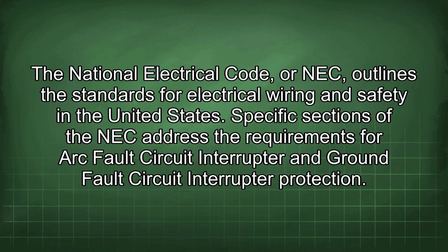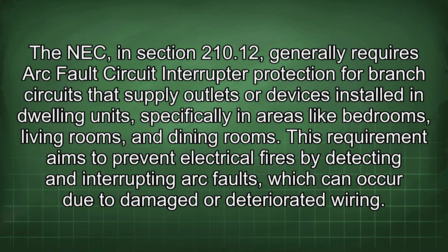The National Electrical Code, or NEC, outlines the standards for electrical wiring and safety in the United States. Specific sections of the NEC address the requirements for arc fault circuit interrupter and ground fault circuit interrupter protection. The NEC, in section 210.12, generally requires arc fault circuit interrupter protection for branch circuits that supply outlets or devices installed in dwelling units, specifically in areas like bedrooms, living rooms, and dining rooms. This requirement aims to prevent electrical fires by detecting and interrupting arc faults, which can occur due to damaged or deteriorated wiring.